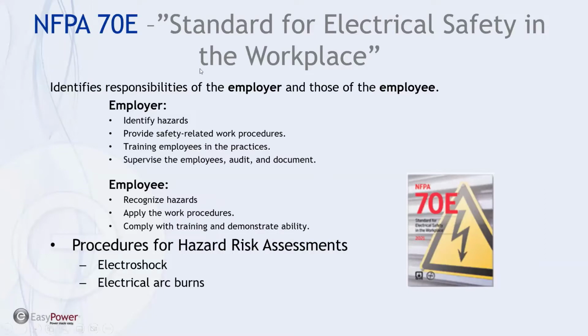So the bottom line for electrical safety in the workplace is NFPA 70E, and it identifies the responsibilities of employers and employees as follows. The employer shall identify the hazard, provide safety-related work procedures, train employees in the practices, supervise the employees, and audit and document the results. The employee, on the other hand, must be able to recognize the hazards and apply work procedures accordingly, and then comply with training and demonstrate ability to do so. This document includes procedures for hazard risk assessment that include electroshock and electrical burns.